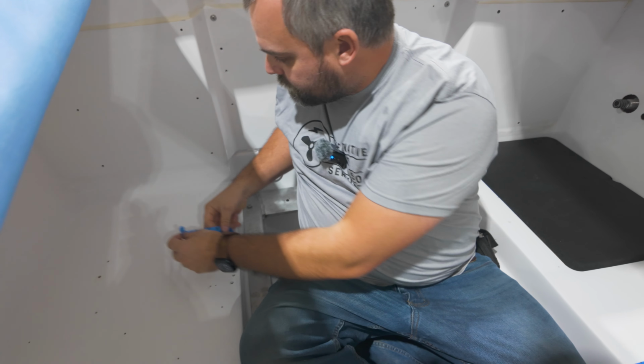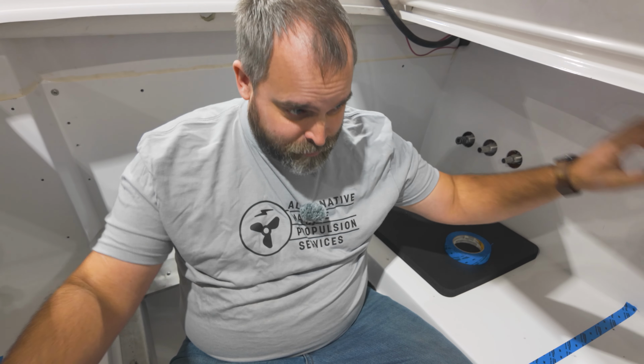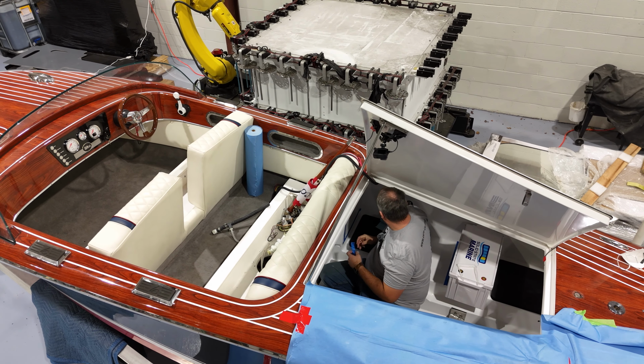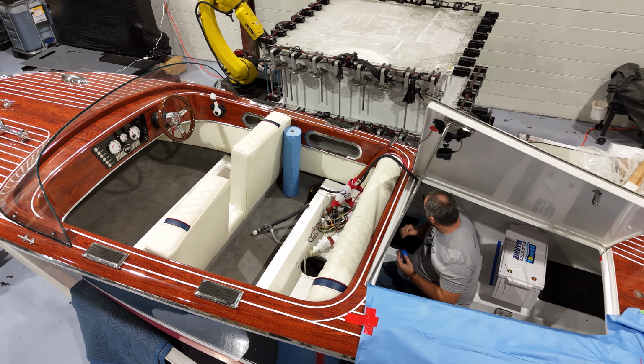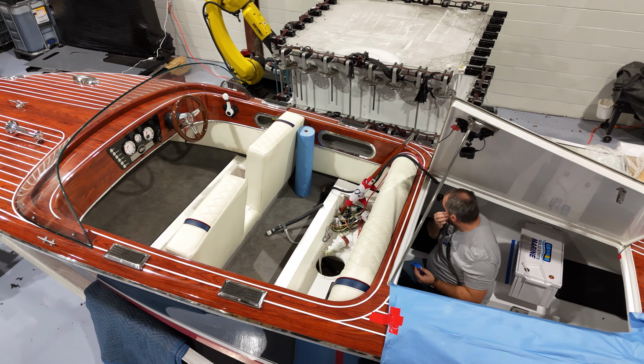Along with the batteries on the battery trays, each battery gets an isolation relay. When you power down the whole system, you can individually shut off each battery, so you're not working with 400 volts at every connection. You can isolate a battery and just take that 48-volt battery out.